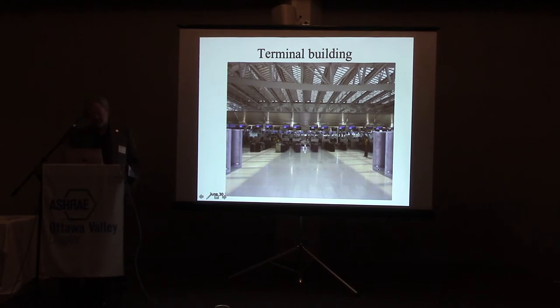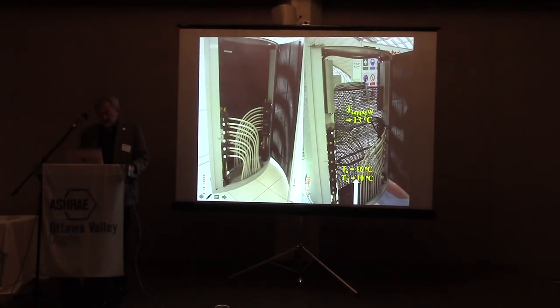They are about, I think, 180 by 140, so they're very large. So one discussion was, yes, but now we want to have a 13 degrees supply temperature of the water. What about condensation on the pipe? Do we have to put in the manifold here? Do we have to insulate so we avoid a lot of condensation?